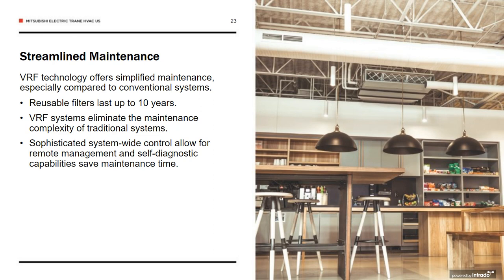A good example of this is a student dorm that I worked on at SFA here in Texas. It's a retrofit that required PTAC units to be pulled out and VRF added in. The savings ended up saving the maintenance crew hundreds of hours a year because they were able to, one, monitor the building remotely just using VRF controls. And they were also able to diagnose things early on before even setting foot on the site.